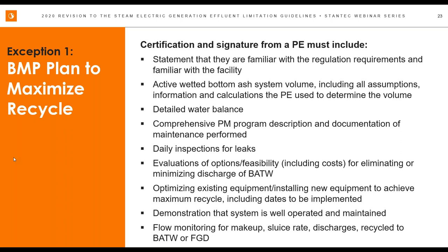Daily inspection for leaks. And daily inspection for leaks doesn't mean when people are available with reduced staffing, and doesn't necessarily mean, as written, just when the units are running. So you need to take a look at that as staffing plans are being shifted and staff are being shared between facilities.